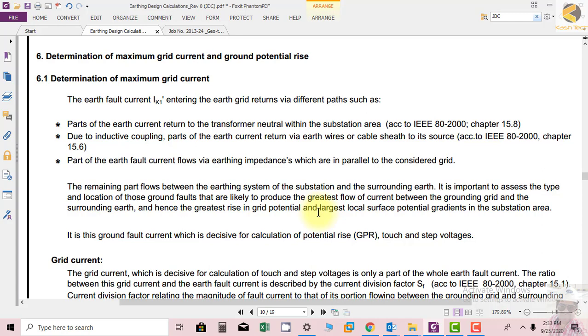To summarize, the different return paths for ground potential rise include: the transformer neutral, inductive coupling via earth wires or cable sheath, and part of the earth fault current flowing through earth impedances that are in parallel with the grounding grid.